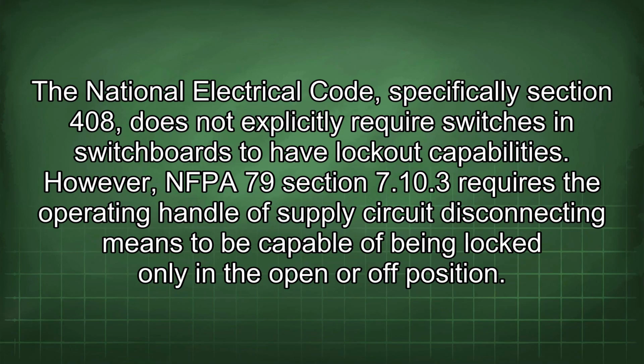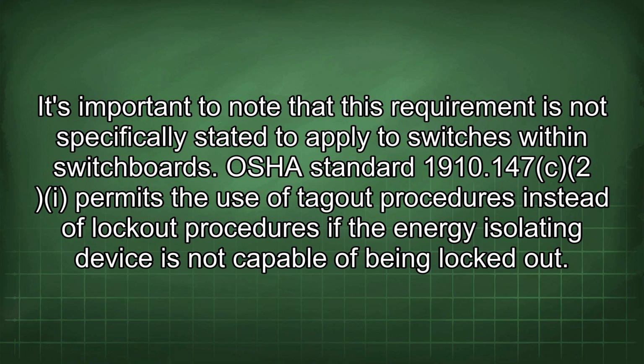The National Electrical Code, specifically Section 408, does not explicitly require switches in switchboards to have lockout capabilities. However, NFPA 79 Section 7.10.3 requires the operating handle of supply circuit disconnecting means to be capable of being locked only in the open or off position. It's important to note that this requirement is not specifically stated to apply to switches within switchboards.